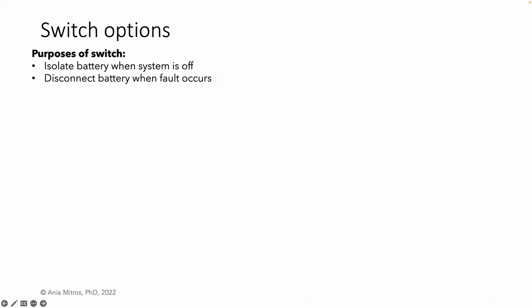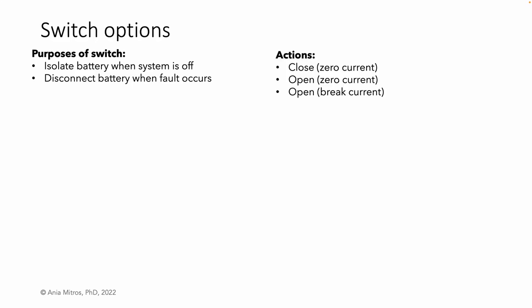Let's review the purposes of the switch. The switch needs to isolate the battery when the system is off and to disconnect the battery when a fault occurs. This corresponds to three possible actions: closing the switch, which happens with zero current flowing because current doesn't flow when a switch is open. Opening the switch with zero current flowing, which is what we do when the system powers down in a controlled fashion, and opening the switch with current flowing, which happens when responding to a fault.